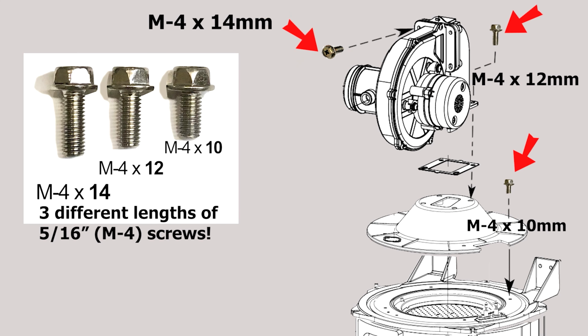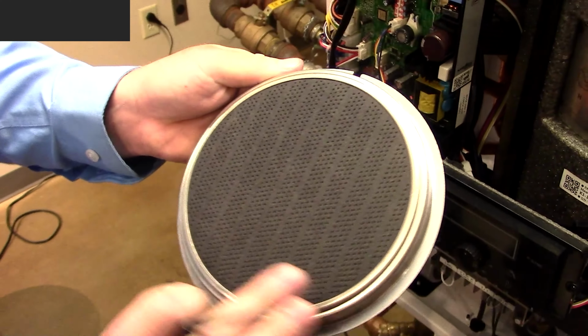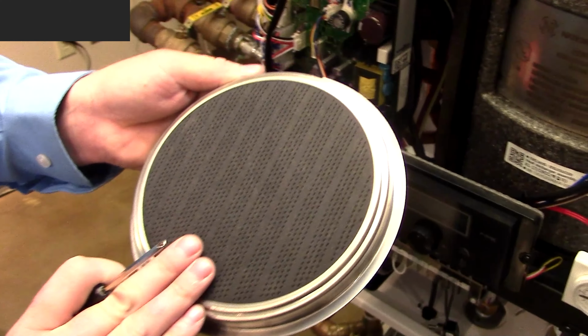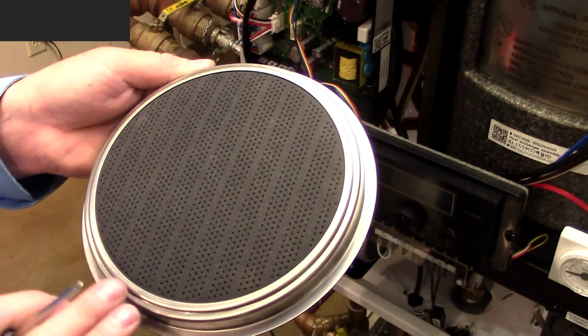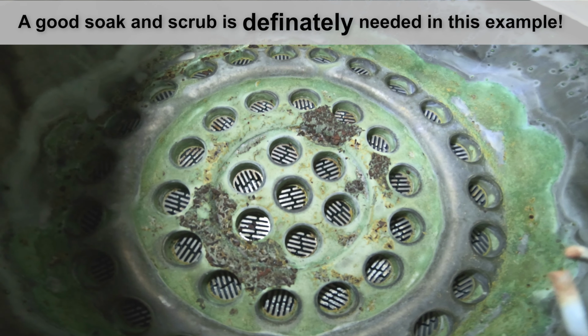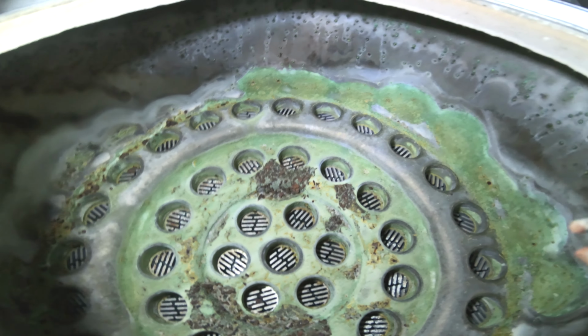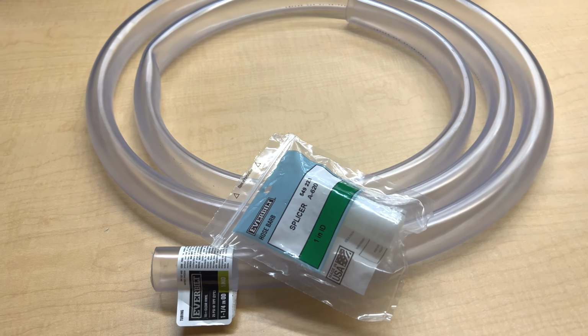Inspect the burner screen very carefully. Do not touch the ceramic fiber with anything other than air. Take a picture if necessary and decide if a full soak and cleaning is needed. To soak these stainless steel fire tube heat exchangers, a clear acrylic 1 1/4 inch OD hose and a 1-inch ID splicer tube must be hose clamped into place of the condensate trap. It's the same tube and tube splicer for all sizes.